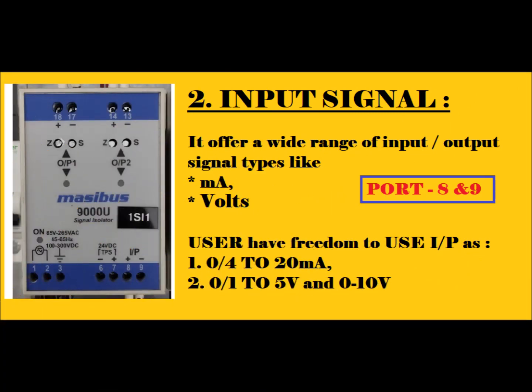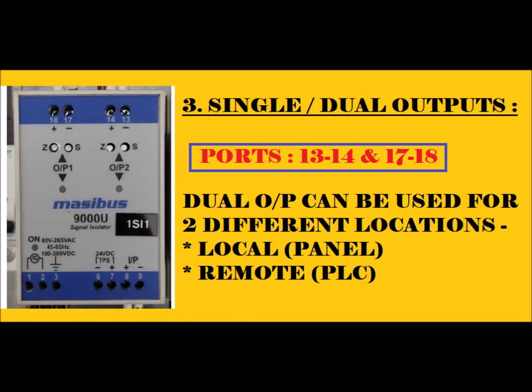Next is the Input Signal. The Signal Isolator accepts a wide range of input signals — generally milliamps or voltage. Port number 8 and 9 are connected to positive and negative, because incoming signals are generally DC and connecting positive and negative terminals correctly is very important. Input range is 0–20mA or 4–20mA, and voltage is 1–5V or 0–10V.